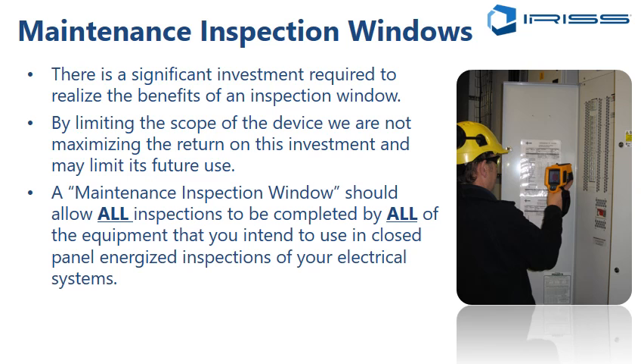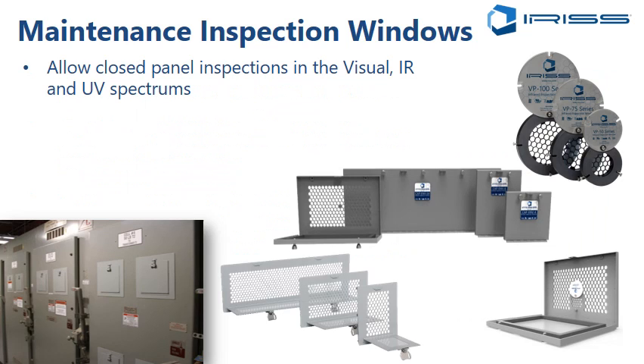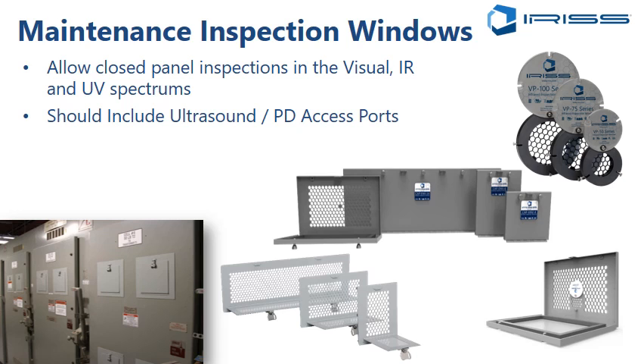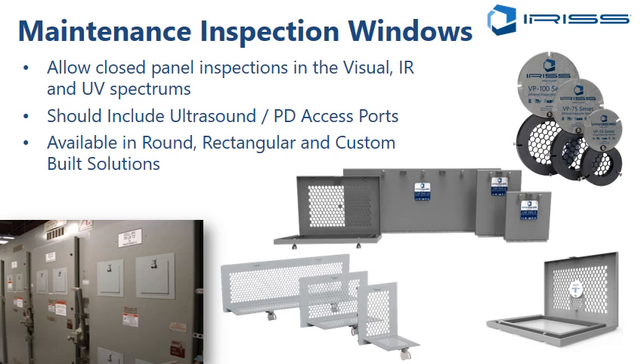So what we say is a maintenance inspection window should allow all inspections to be completed by all of the equipment that you intend to use in a closed panel energized inspection of your electrical systems. The maintenance inspection window should allow closed panel inspections of visual, infrared and UV, ultraviolet spectrums, should include ultrasound and partial discharge access points, and should be available not just in round, but round, rectangular or custom built solutions. And custom built solutions are becoming extremely popular.